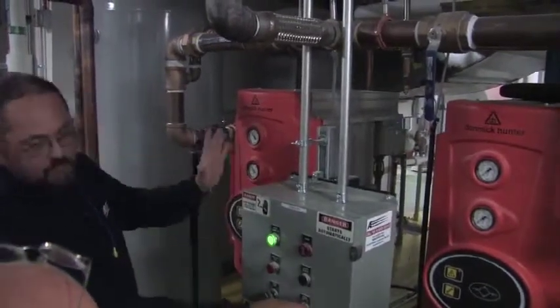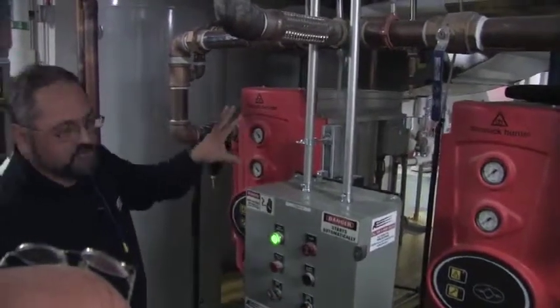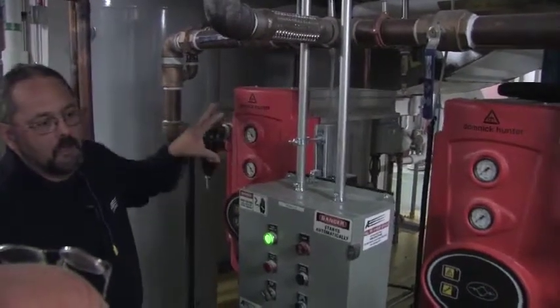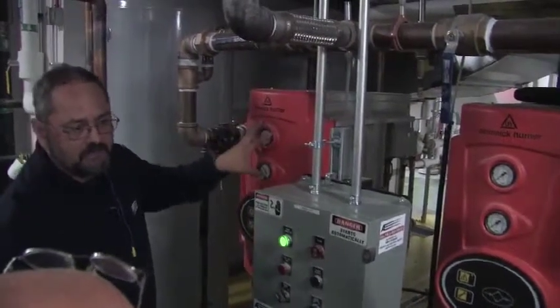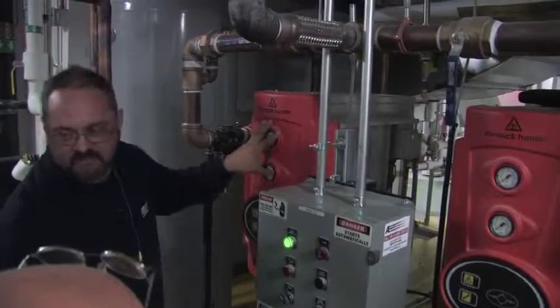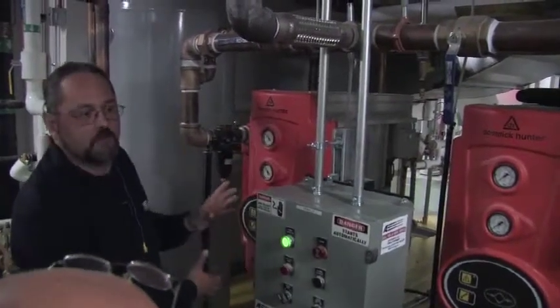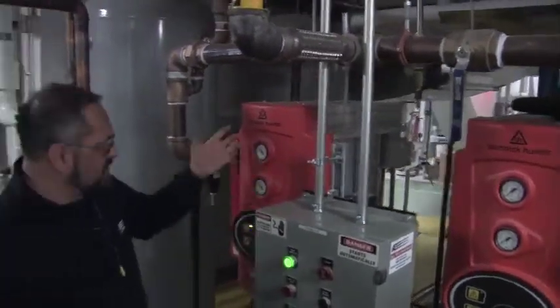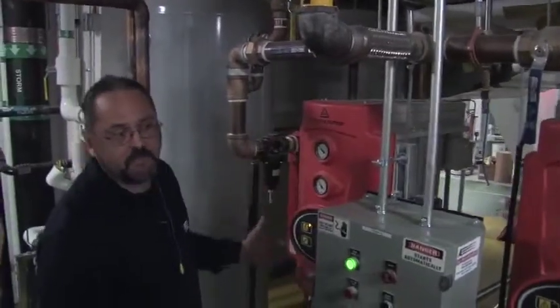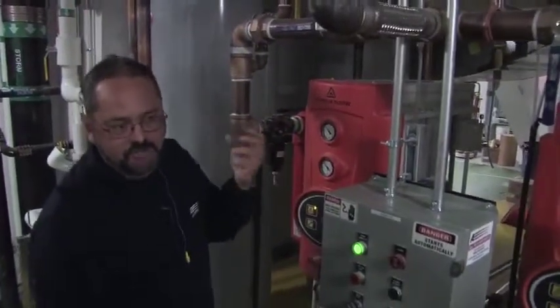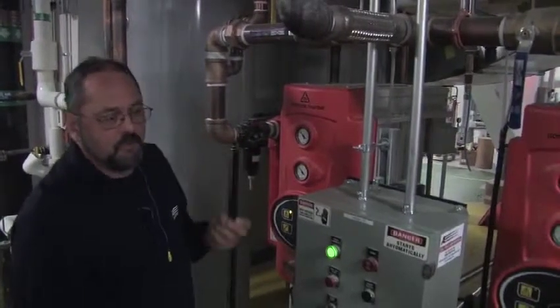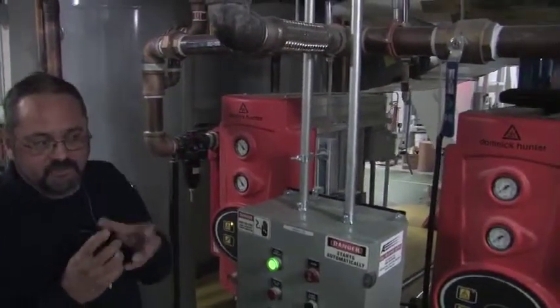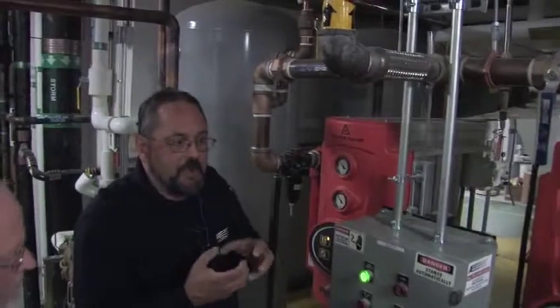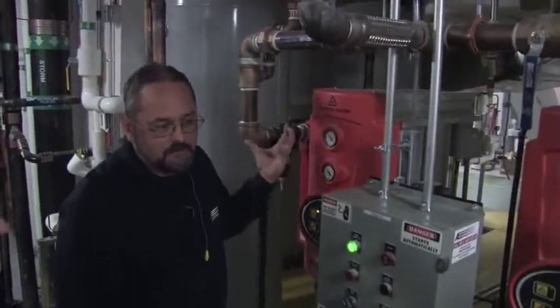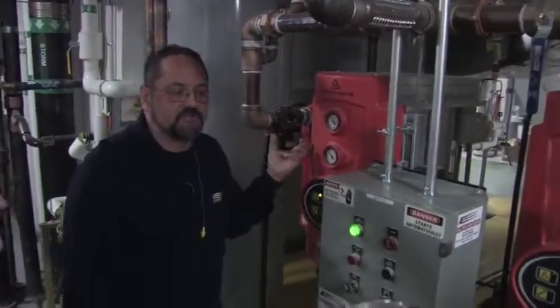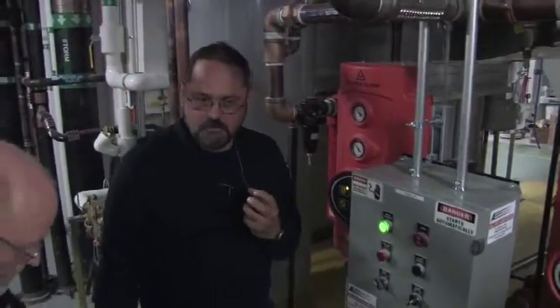The real reason for this purge saver is that when this is running, 15% of its air capacity gets vented out that muffler to dry the stuff out. Think of it like a sponge. There are literally hundreds or thousands of beads in here that look like little beige or brown BBs. Under a microscope, there are literally hundreds of square feet of surface area in that bead. They don't get mushy like a sponge, but basically the beads are designed to trap water vapor.